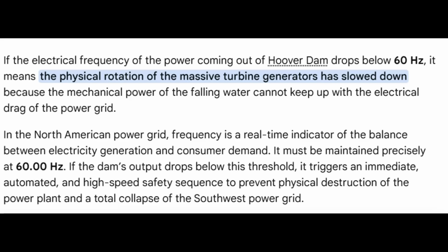Now again, when you shut down that much, it's going to slow down the rotation of the massive turbine generators. They operate at 60 hertz, remember that? And the physical rotation of these turbines has slowed down because the mechanical power of the falling water cannot keep up with the electrical drag of the power grid. In the North American power grid, the frequency is a real-time indicator of the balance between electricity generation and consumer demand, and it is, guys, they watch that very closely. It must be maintained precisely at 60 hertz. If the dam's output drops below this threshold, it triggers an immediate automated and high-speed safety sequence to prevent physical destruction of the power plant and the total collapse of the Southwest power grid.